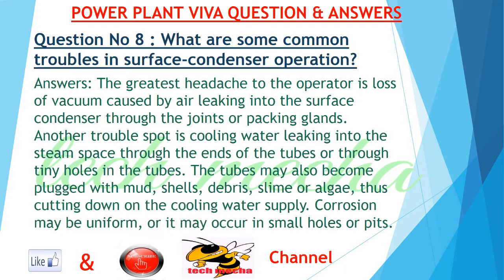Question number 8: What are some common troubles in surface condenser operation? Answer: The greatest headache to the operator is loss of vacuum caused by air leaking into the surface condenser through the joints or packing glands. Another trouble spot is cooling water leaking into the steam space through the ends of the tubes, or through tiny holes in the tubes. The tubes may also become plugged with mud, shells, debris, slime, or algae, thus cutting down on the cooling water supply. Corrosion may be uniform, or it may occur in small holes or pits.